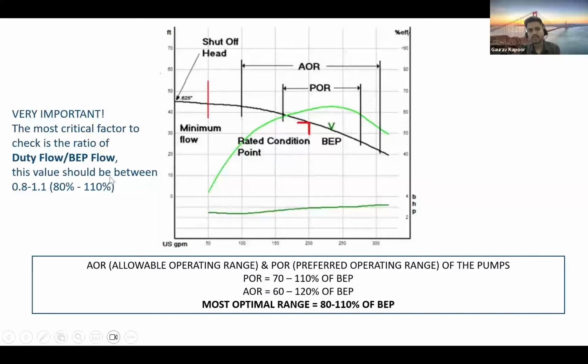Now how to check this 80 to 100%? It's very easy. Whatever your duty flow is divided by the BEP flow, the majority of the manufacturers give them in their data sheet, but if you're unable to find it, it is very easy to see.